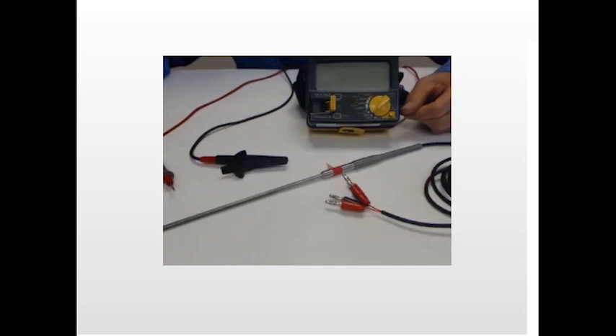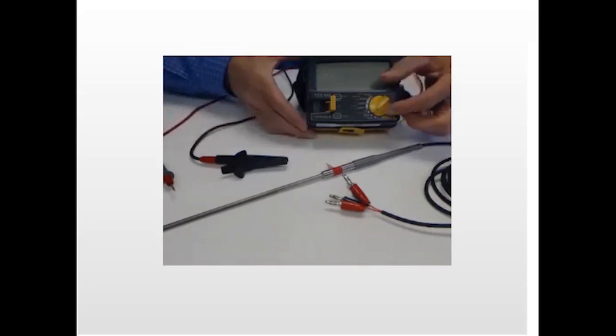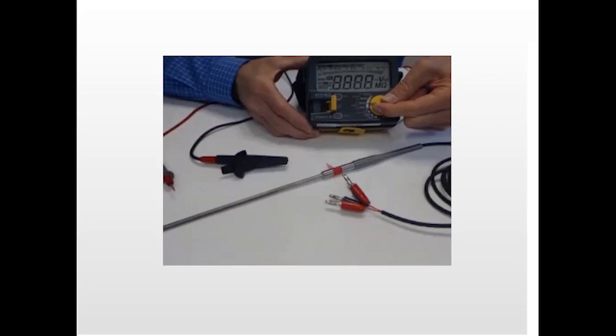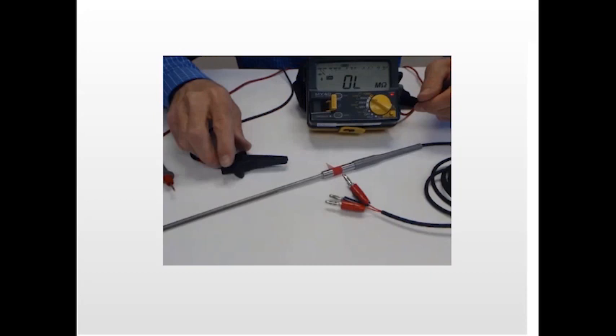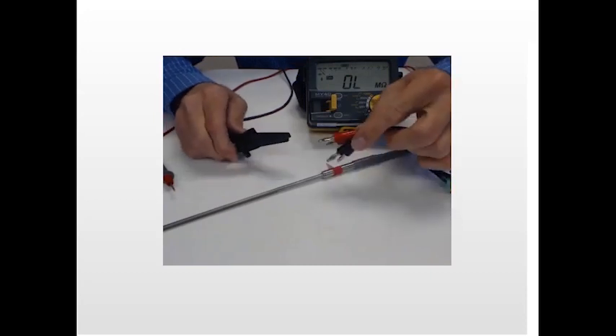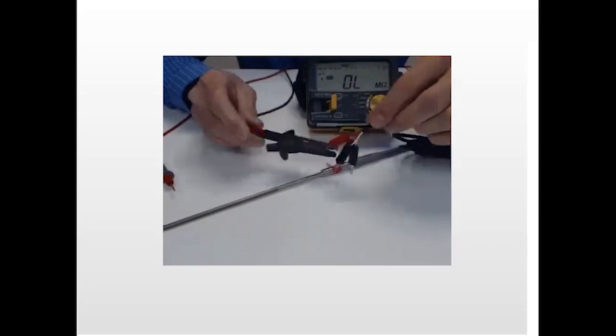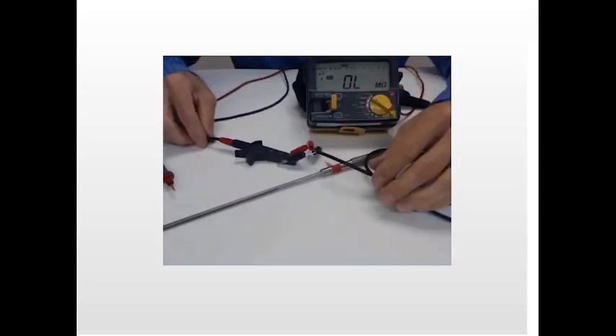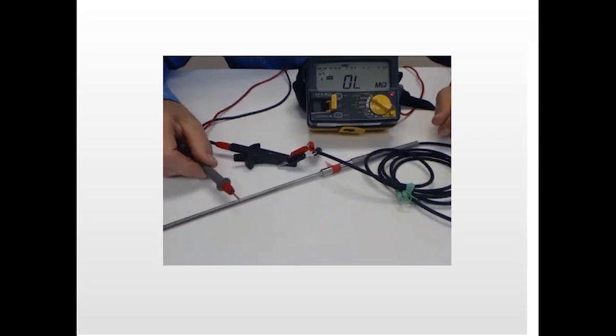We're going to start out with a probe that's actually bad here, and we've got this megohm meter, and we'll set this one to the 200. There's a 500 volt scale right there, and just connect one of the lead wires to the probe leads. You can bundle them together, or typically just use one of them. If it's bad, you're going to get a bad reading typically. And here we can see this one is quite bad. We got 0.04 something megohms. So this one has a really major problem.